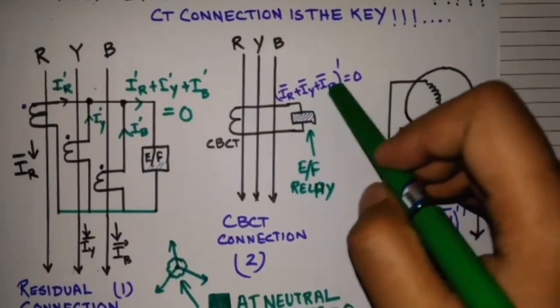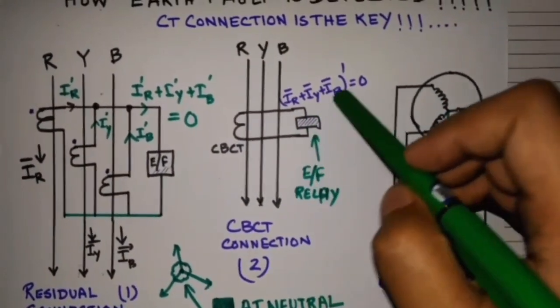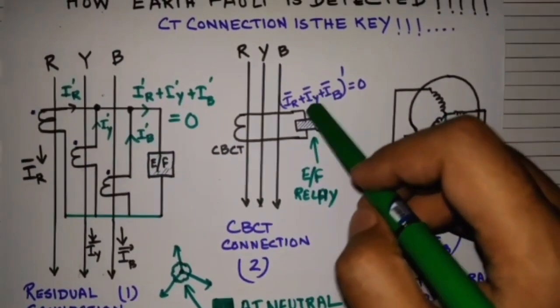So here at first the summation is done, IR, IY, IB, then it is divided by the CT ratio. So here also in normal operating condition the summation will be zero, but when there is an earth fault it will not be zero.